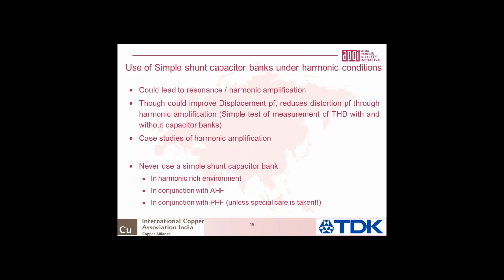On the simple test I've seen, you measure the total harmonic distortion in current and voltage with and without capacitor banks. I'm sure in at least one third of the cases you would see the harmonic distortion comes down when you disconnect the capacitor banks, especially if these are simple capacitor banks without any series reactors.